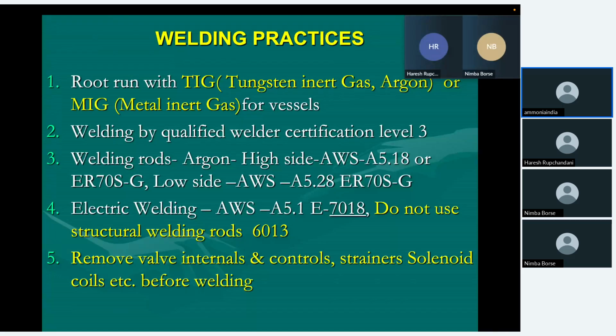Then one of the most important points, if you are doing the welding anywhere on an installed plant, remove all valve internals, because valve internals could be of rubber, neoprene, or some other material which cannot withstand such high temperatures which come during welding. Remove all controls, remove all strainers, remove all solenoids before doing any welding. If you don't do this, your controls or some parts may get damaged.